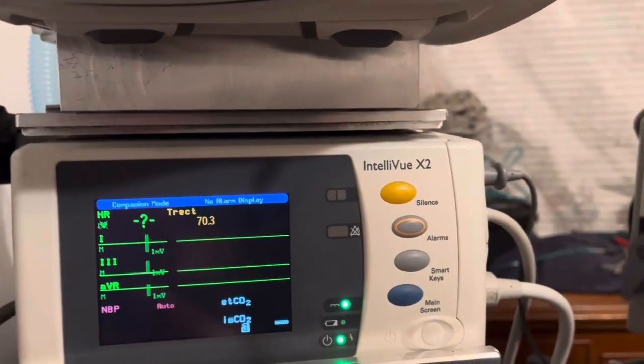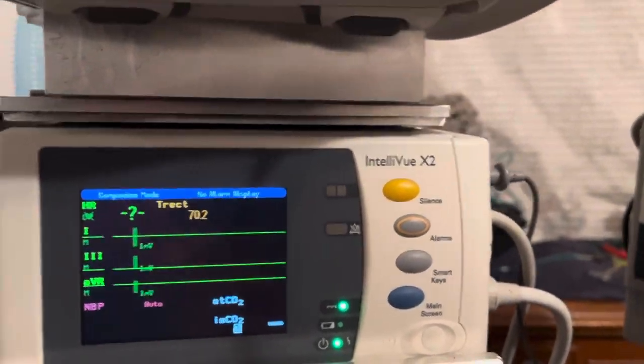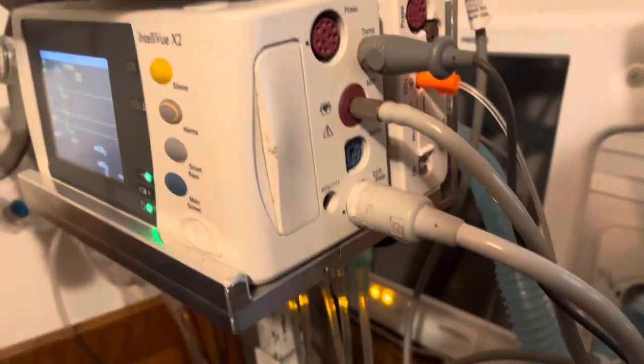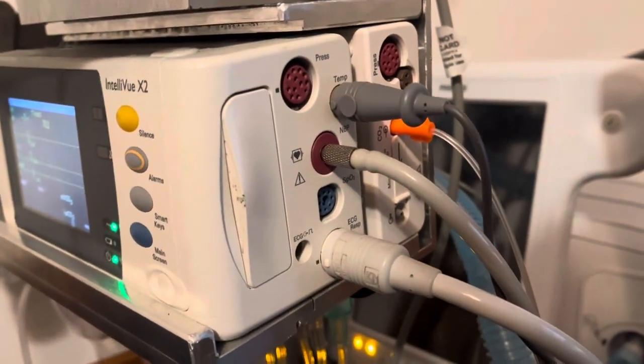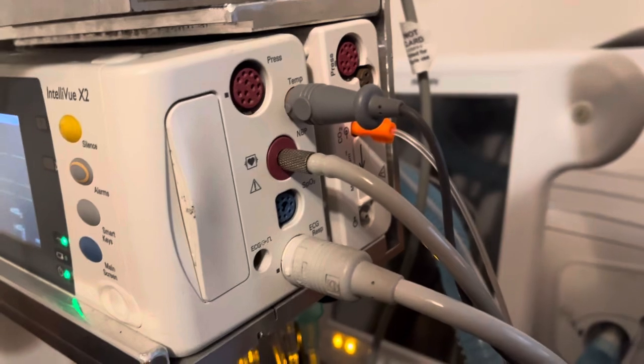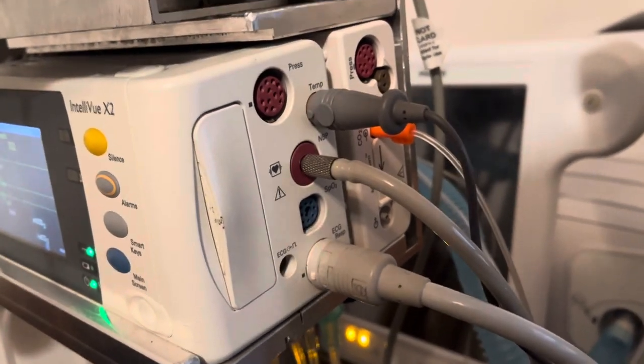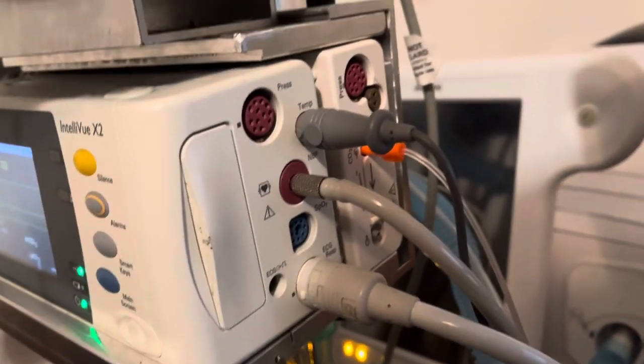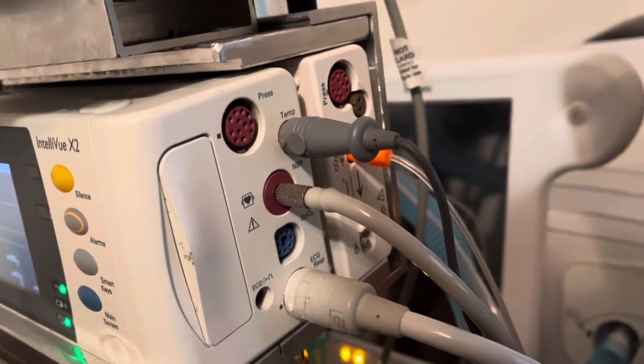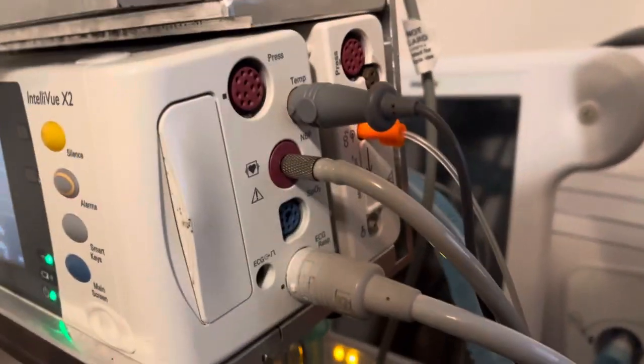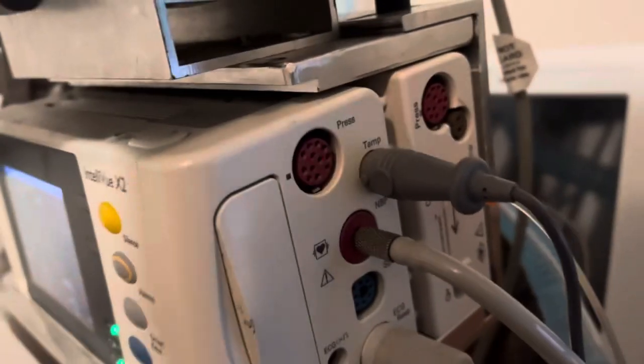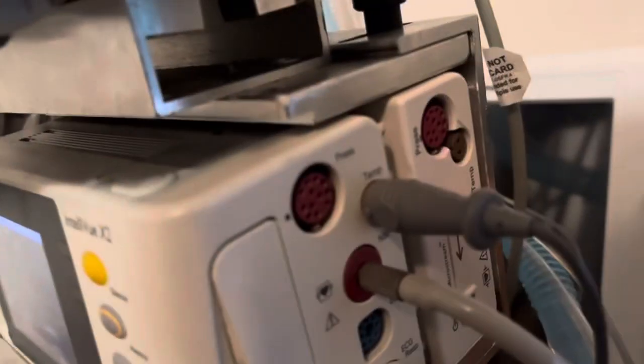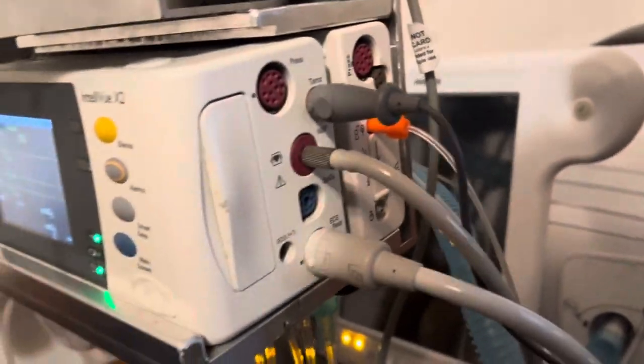This is 3 waves, and I usually show different waves than what's on the MP50 because I can get 3 more waves out of it. And the inputs on the side, we've got fast SpO2, ECG resp, NBP, temp, and then behind it I have an M3015A CO2 extension module with microstream CO2, another press input, and a temp input. That would be the CO6 option.